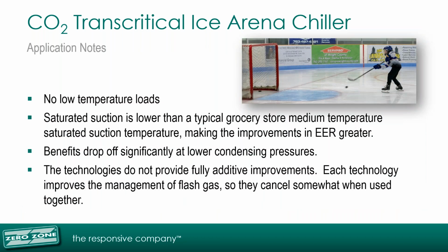The ice rink has a few differences when compared to grocery stores and some other details I would like to review with you. There are no low temperature loads, so our EER is higher than a grocery store would experience. The saturated suction temperature is lower than a typical grocery store's medium temperature saturated suction temperature, so our EER improvements with the adiabatic cooler and parallel compressor are greater. The benefits of an adiabatic condenser and parallel compressor drop off significantly at lower ambient temperatures. The annual operating conditions for the equipment need to be evaluated when making design decisions on what to include in your system. The technologies did not provide fully additive improvements. Each technology improves the management of flash gas, so they cancel somewhat when used together. This was shown in the stepwise improvements in the EER values.